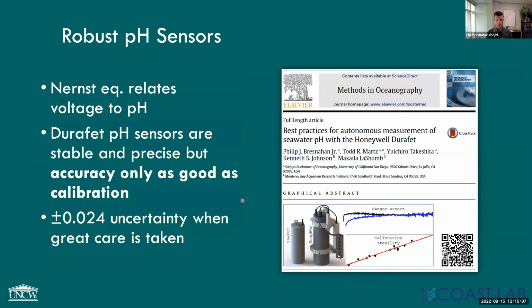What is really great about the sensor is that they're extremely stable and they're extremely precise, but they relate pH to a voltage through the Nernst equation, which if you haven't taken Chemistry 101 in a while, I'm not actually going to bother to show the equation other than to say that the Nernst equation has a constant in it, which is an offset which has to be determined through a manual calibration. There's no theory that will allow us to get to this constant. And so therefore, the accuracy for these devices is only as good as the calibration.